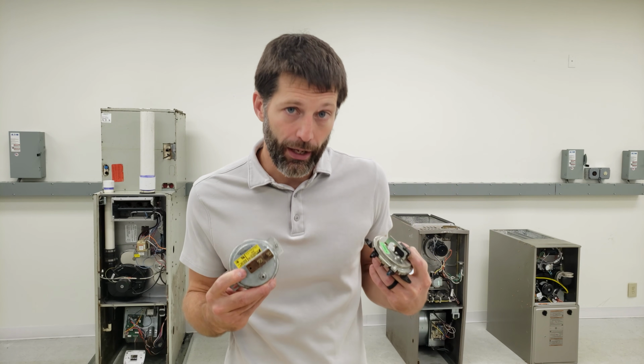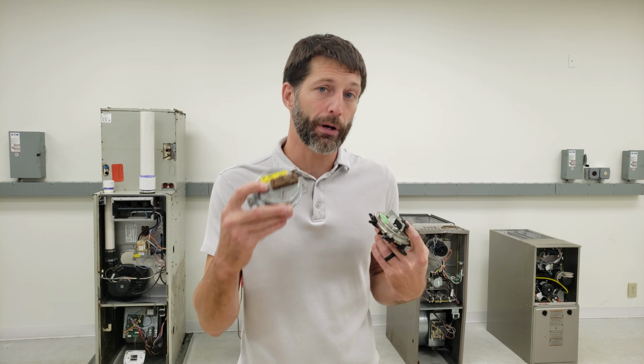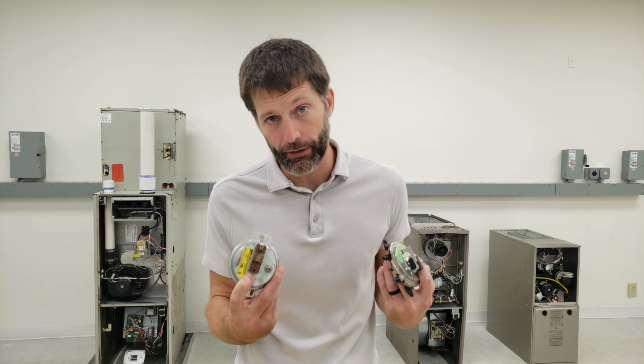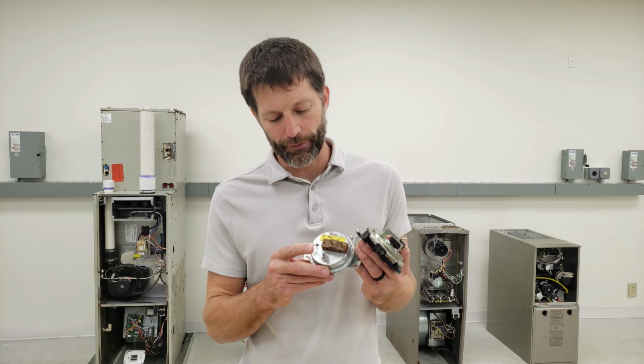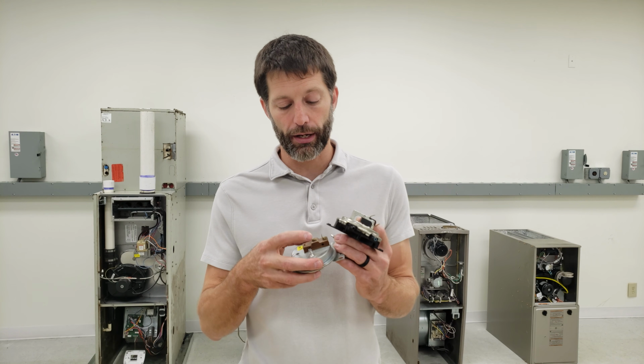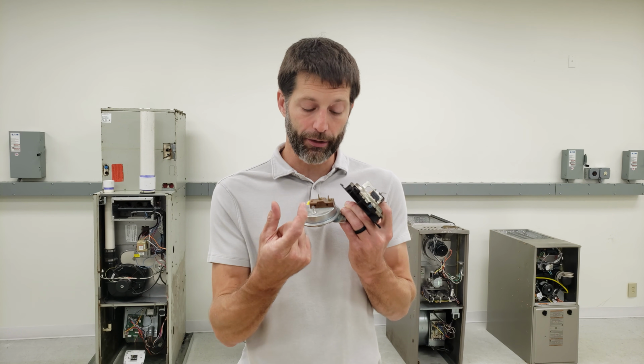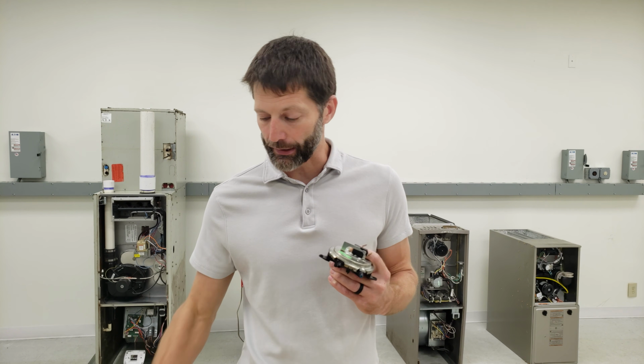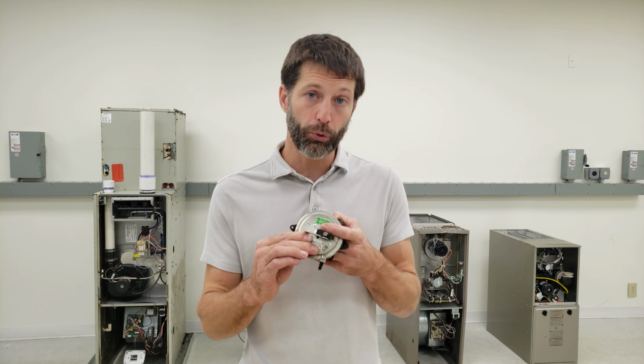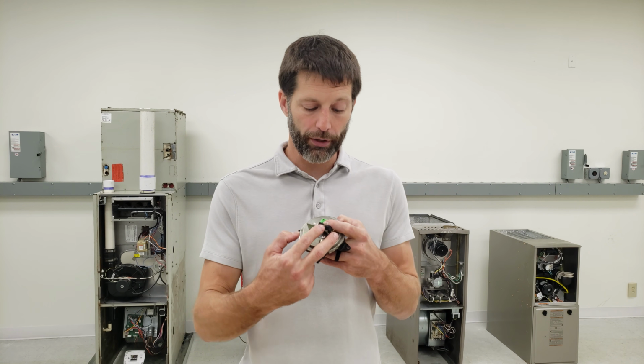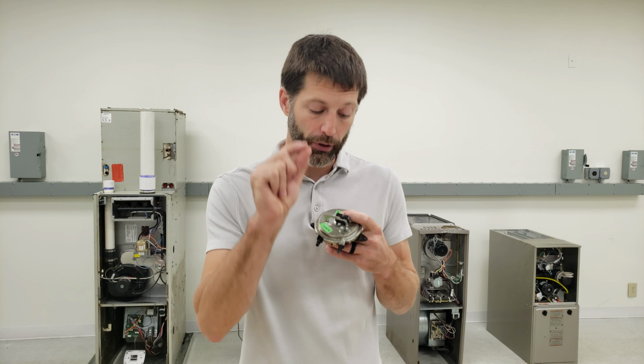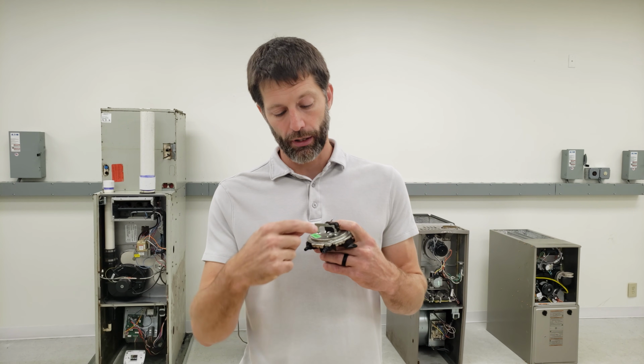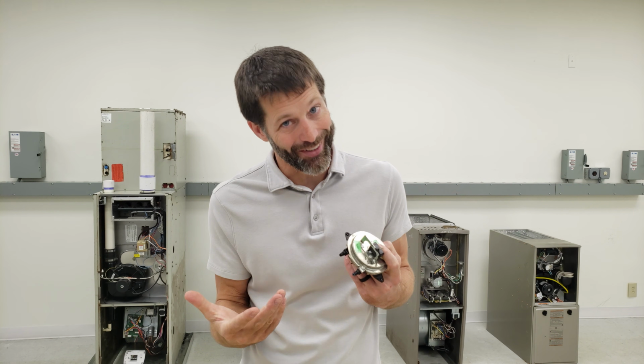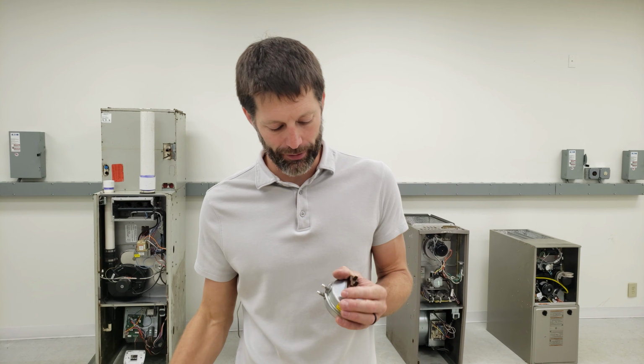So not only do you have plastic pressure switches, there are also metal ones out there as well, and they function basically the same way. In this case, you have a single port pressure switch, and you have normally open sets of contacts just like the other one. You could have a two-port pressure switch like this with a set of normally open contacts that will close when there's a pressure reduction of a differential basically across the switch, which I'll explain in a sec.